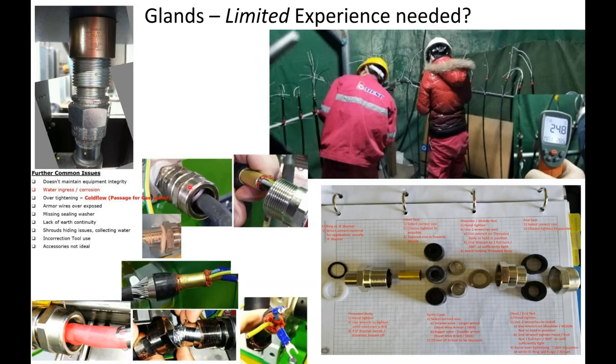These cable glands, we were looking at a 95% failure rate. So what we did is we defined a training program using memes, pictures, with words. The manufacturer's instructions, perhaps manufacturers are not competent in how to install their glands. Perhaps they're just manufacturing and selling things. It would be in their best interest.